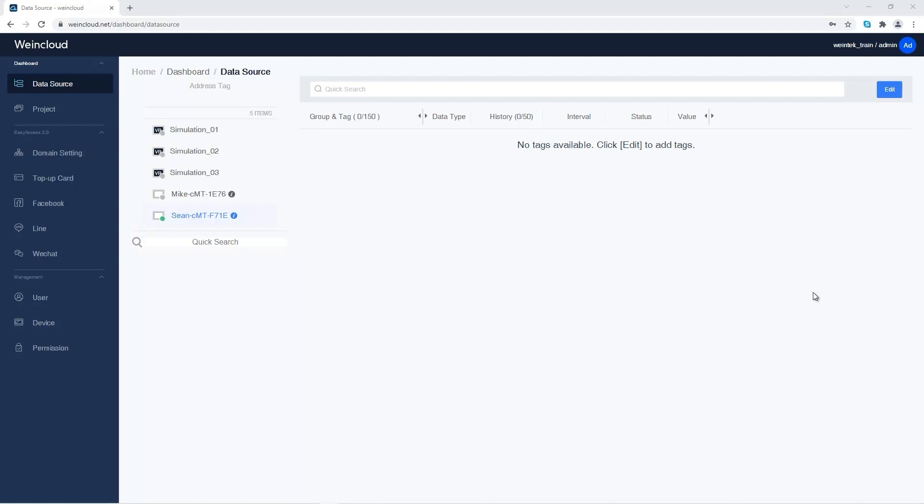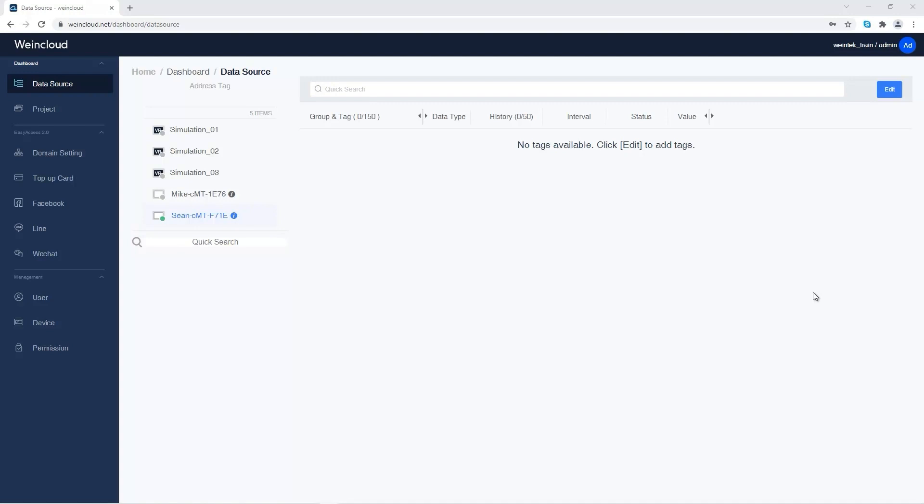This is where to manage the data to be displayed on dashboard. Here I can define the tags from machines online status to OEE of machines. In data source, you can choose a simulation or an actual HMI. If I create tags in simulation, I need to run online simulation in EasyBuilder Pro. If I create tags in an actual HMI, I need to download the EasyBuilder Pro project into that HMI. Let's choose an actual HMI here.